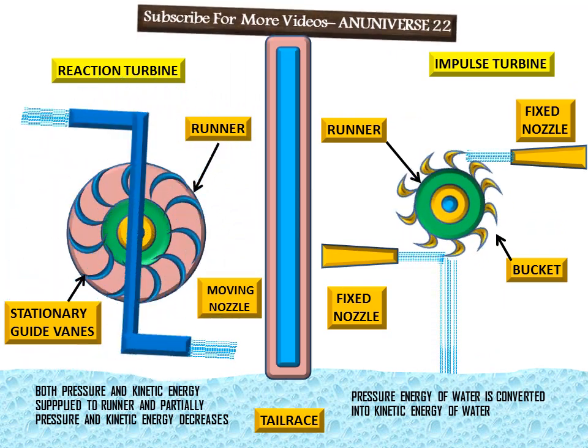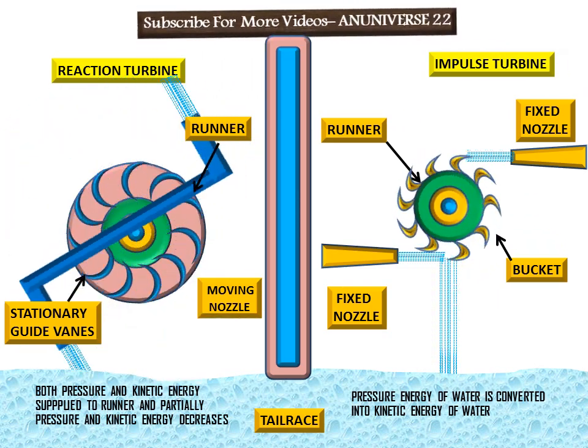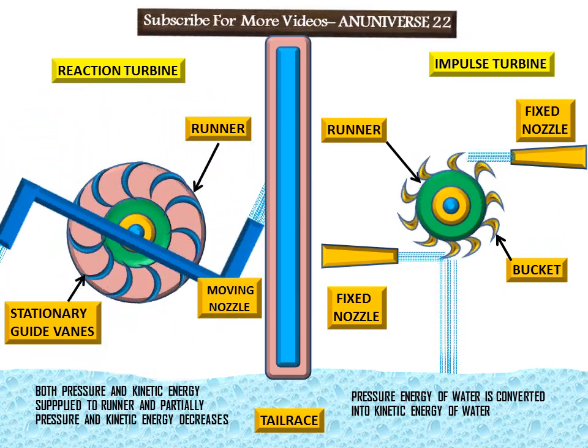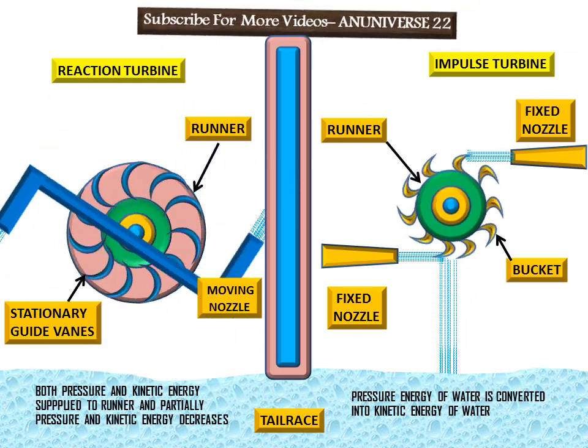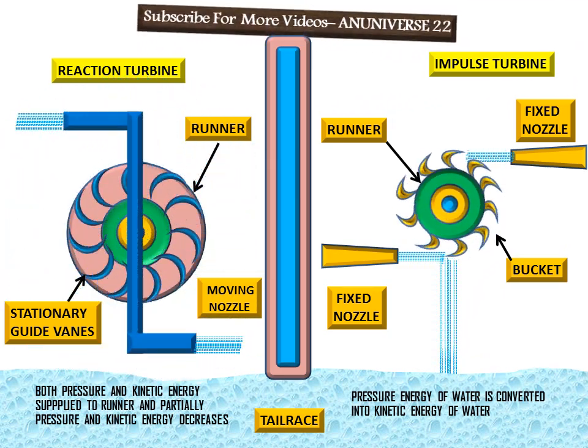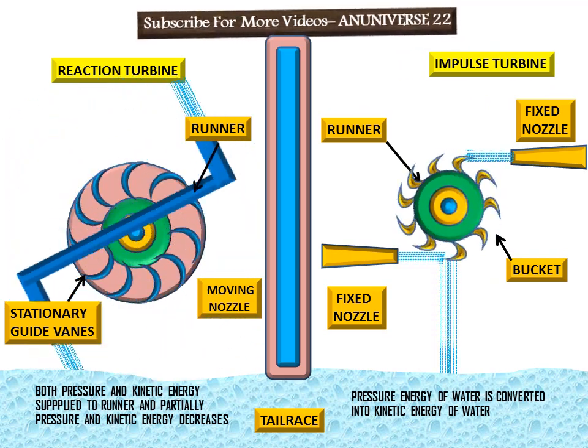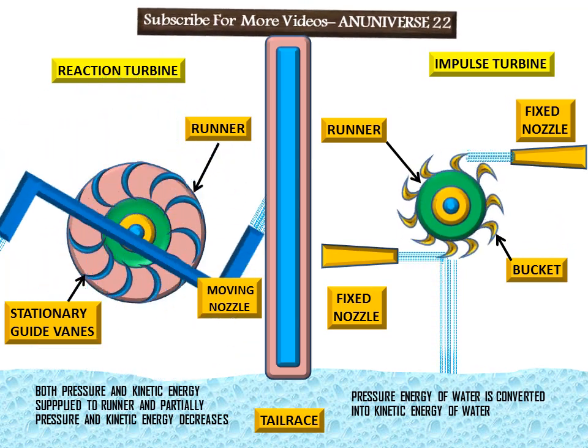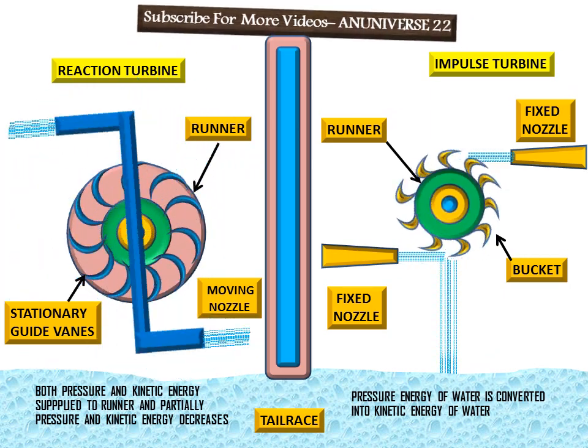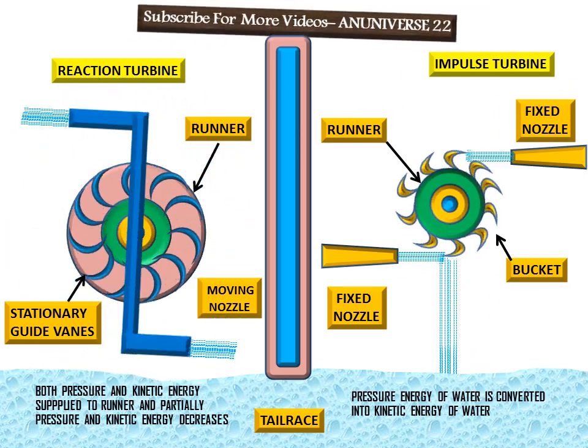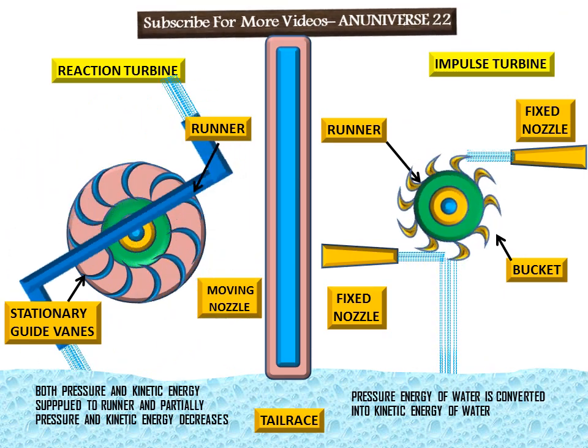The reaction turbine is completely enclosed by a casing. A tube connected at the outlet of the turbine to the tailrace is known as a draft tube, and its purpose is to raise the effective head acting on the turbine. In the impulse turbine, no draft tube is needed since it operates at atmospheric pressure. However, in the reaction turbine, pressure varies, so a draft tube is required to maintain the effective head.